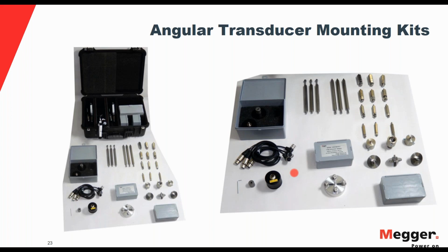A lot of manufacturers already define some mounting points and they already do the test in the factory and also maybe in the commissioning stage. So even for routine maintenance, you can do this test as well from the same point. So you can get a consistent result with what they get in the commissioning and factory acceptance testing.